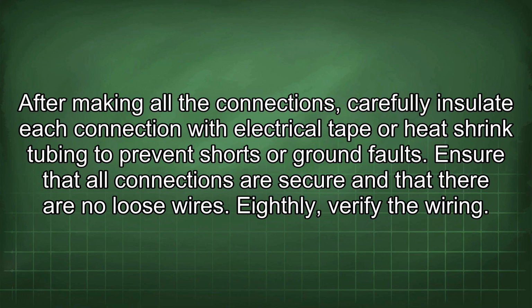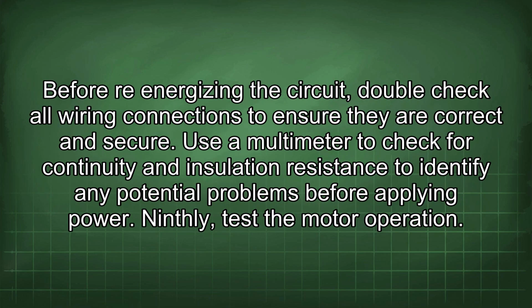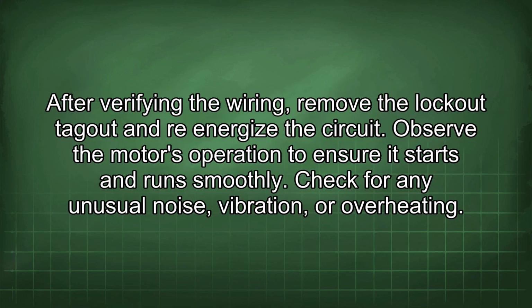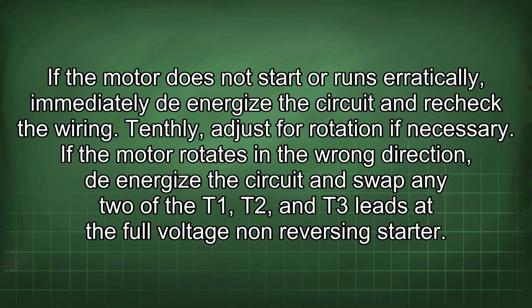Eighthly, verify the wiring. Before re-energizing the circuit, double-check all wiring connections to ensure they are correct and secure. Use a multimeter to check for continuity and insulation resistance to identify any potential problems before applying power. Ninthly, test the motor operation. After verifying the wiring, remove the lockout tagout and re-energize the circuit. Observe the motor's operation to ensure it starts and runs smoothly. Check for any unusual noise, vibration, or overheating. If the motor does not start or runs erratically, immediately de-energize the circuit and recheck the wiring.